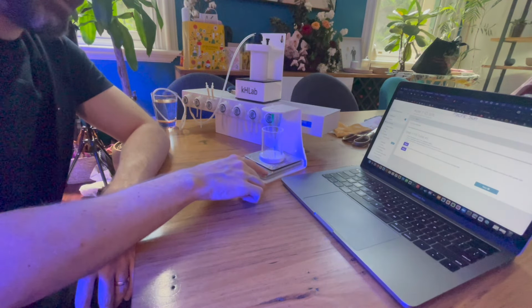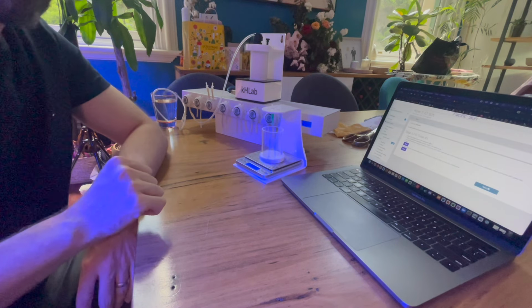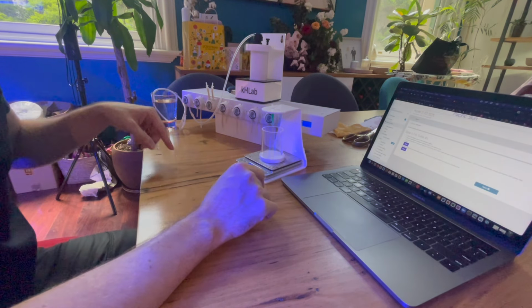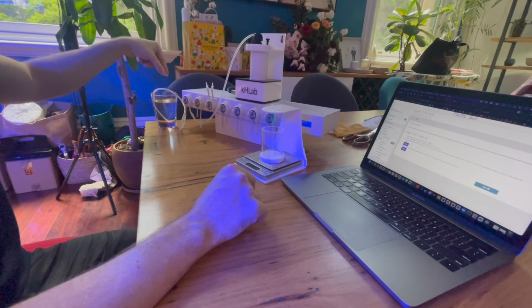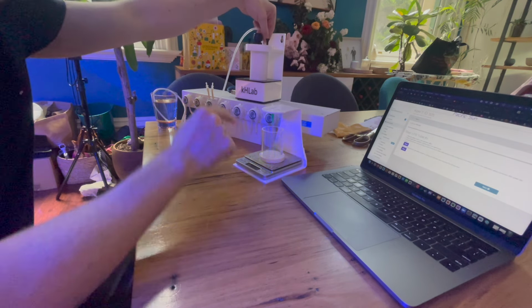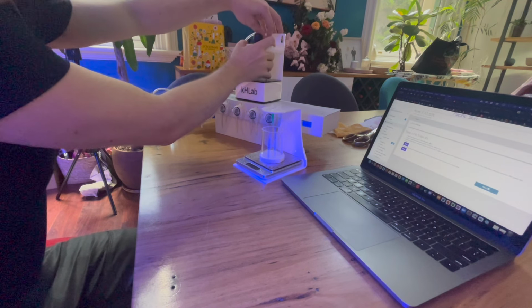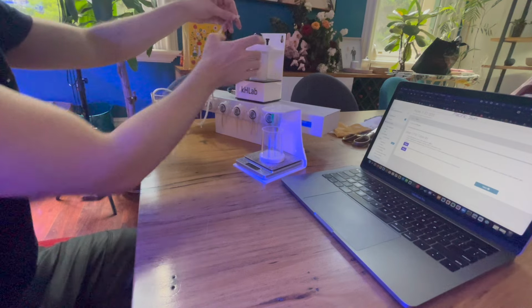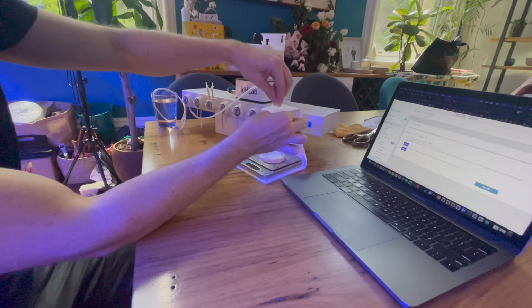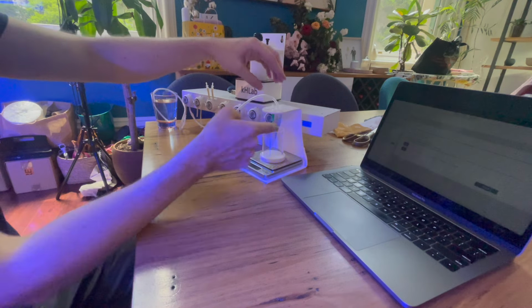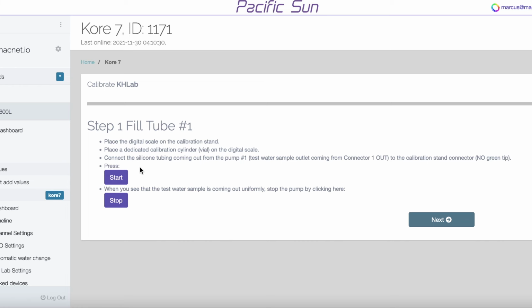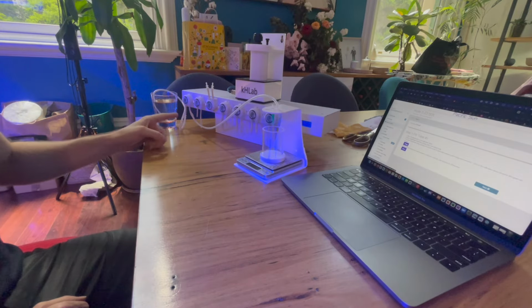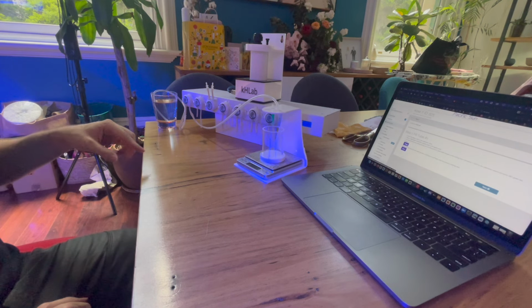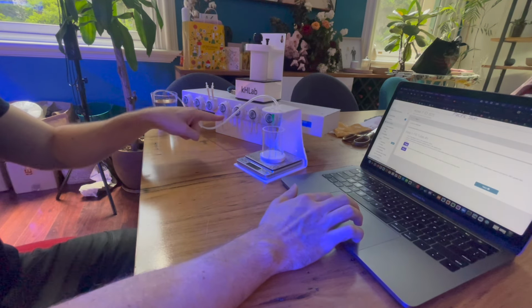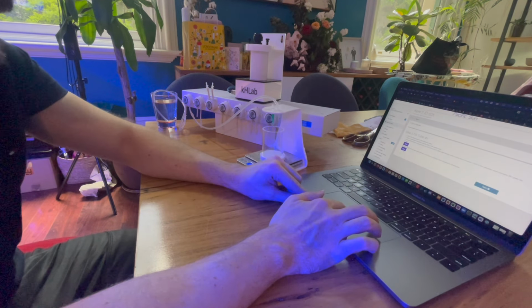So yeah, you want to press the T button here after you've turned the scale on, and that resets it to 0. Then what you want to do is connect the silicon tubing that normally goes into the KHLab here for pump 1, which is the water in. You want to disconnect it from the KHLab and connect it to the second port on here, which is the one without the green tip on it, so just the open one. Simple as that. Then you just want to press start on the screen, and you can see the pump turns on, and all we're doing right now is priming the line. So you just want to leave it running. We can see water running through the line, and as soon as water starts coming out, you press stop.